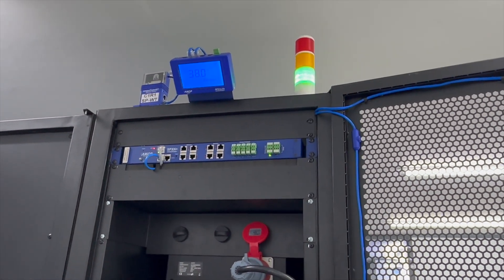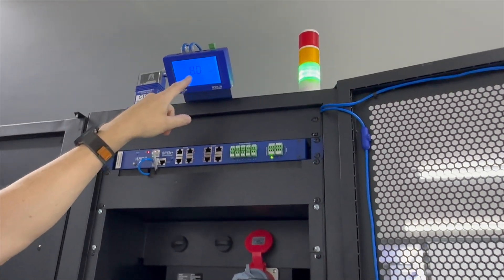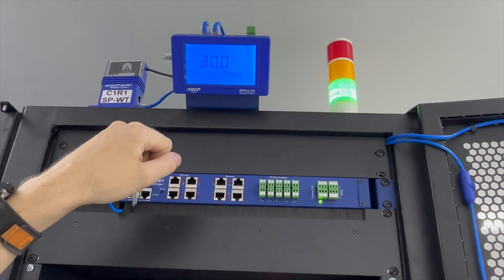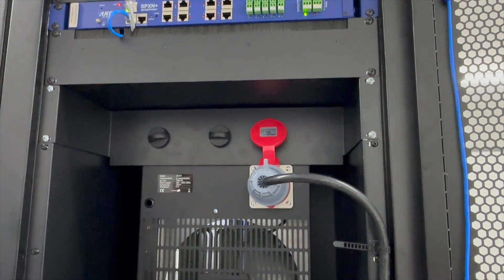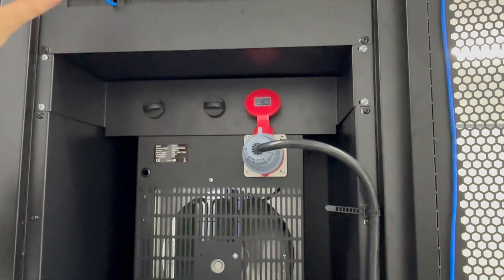Our containment will be installed next. The LCD display is running through — currently this rack is consuming eight kilowatts. We've got a temperature in of 30 degrees and a temperature out of 38 degrees. We just adjusted the thermostats on these heaters to maintain around 38 degrees at the rear.